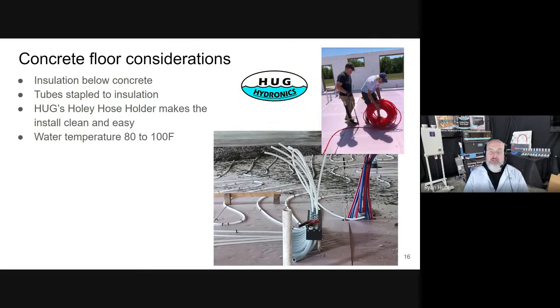So, the concrete floor considerations. Concrete is the most popular thing to heat with in-floor heat, because honestly, cold concrete feels colder than a wooden floor. It sucks the heat out of your feet more. You always need insulation underneath it. Typically, the way it's done today is tubes stapled to the insulation, with little plastic staples and a machine.